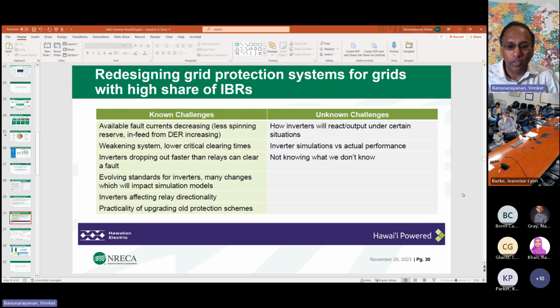Protection systems is a whole different field. We have merely scratched the surface on that. How do you design or reconfigure distribution protection systems for when you have a majority of inverter-based resources, either generation or loads? Most of the distribution protection is based on overcurrent relays, right? The simplest one, overcurrent relays. Well, if you don't have a high enough fault current, you've just rendered that not very usable. So do you use distance relays, which are expensive? So how do you use that?